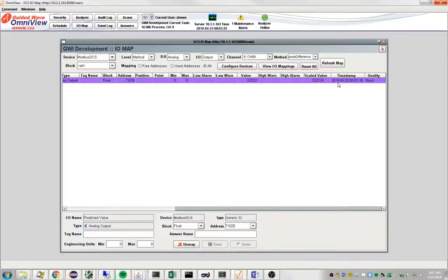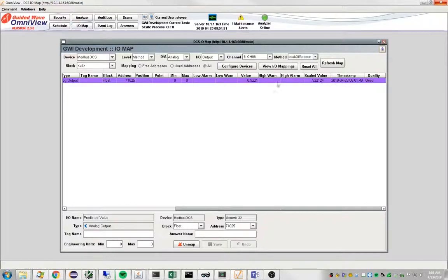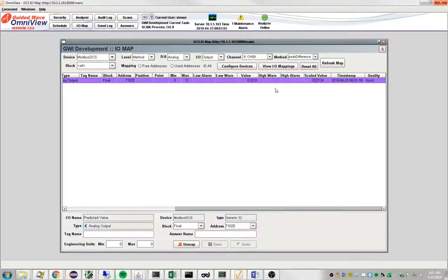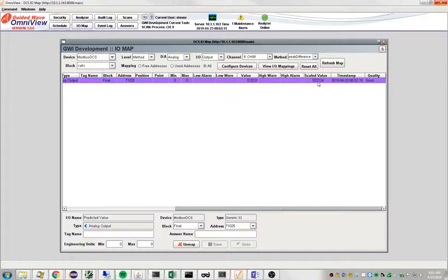The final columns out here show you the time that we wrote that value out and whether it was successful or not. Omniview writes these values out on a recurring basis. I think it's every five seconds. We go out and look up the latest value for this method and we write it out. It's important to remember that if the method gets taken offline and is not producing numbers anymore, what you'll see is this number will not change. The last value will be written out over and over again.